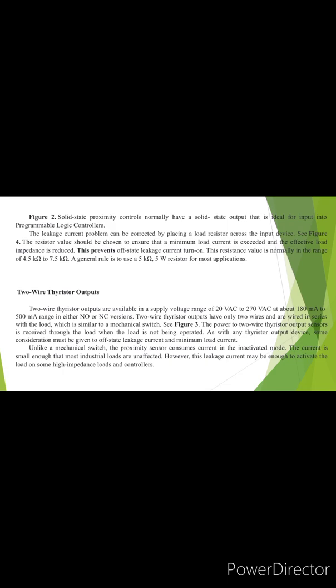The leakage current problem can be corrected by placing a load resistor across the input device. See Figure 4. The resistor value should be chosen to ensure that a minimum load current is exceeded and the effective load impedance is reduced. This prevents off-state leakage current turn on. This resistance value is normally in the range of 4.5 k ohms to 7.5 k ohms. A general rule is to use a 5,000 ohm, 5 watt resistor for most applications.